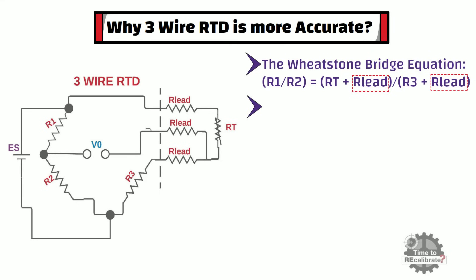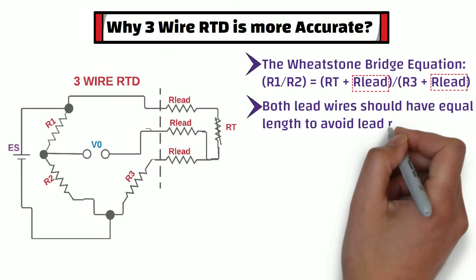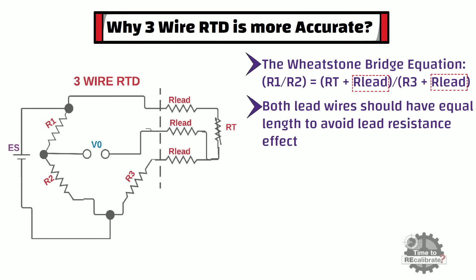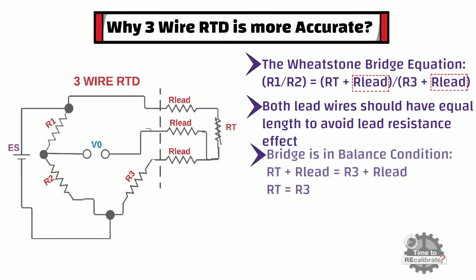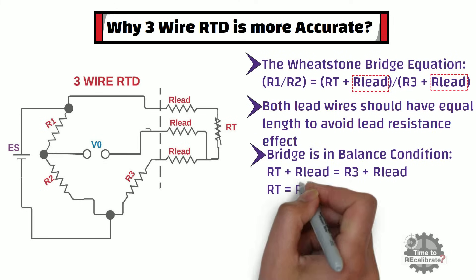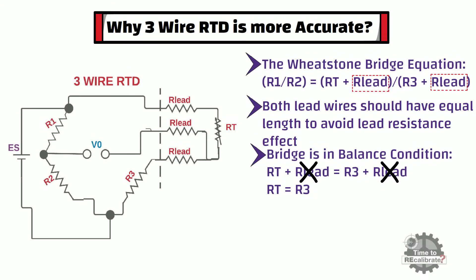However, both lead wires should have equal lengths to avoid lead resistance effect in the circuit. As you can see, this is the equation when the Wheatstone Bridge is in balance condition. In this equation, lead resistance cancels each other with the help of a third lead wire, and this is the reason that temperature measurement does not get affected due to lead resistance.